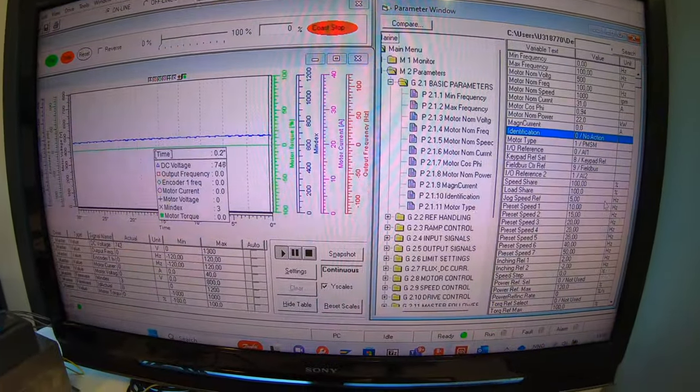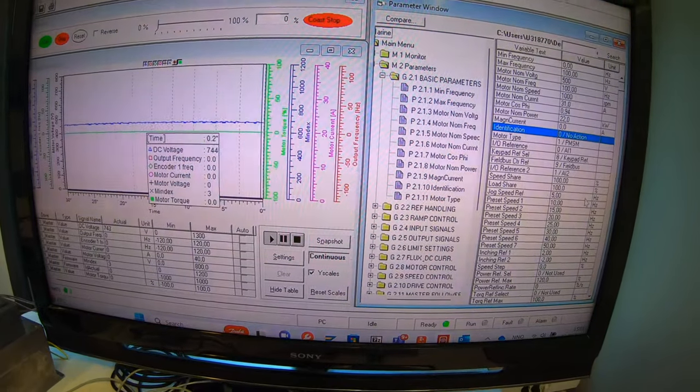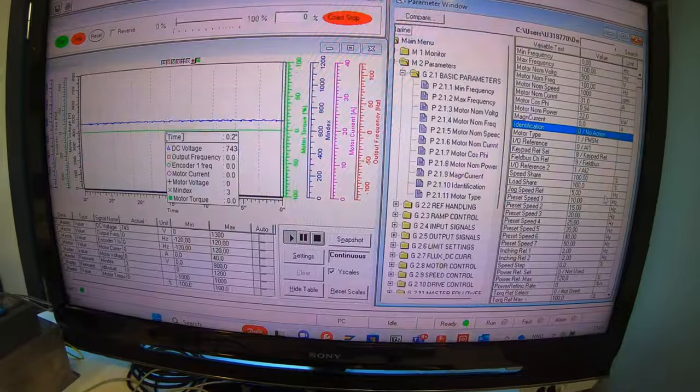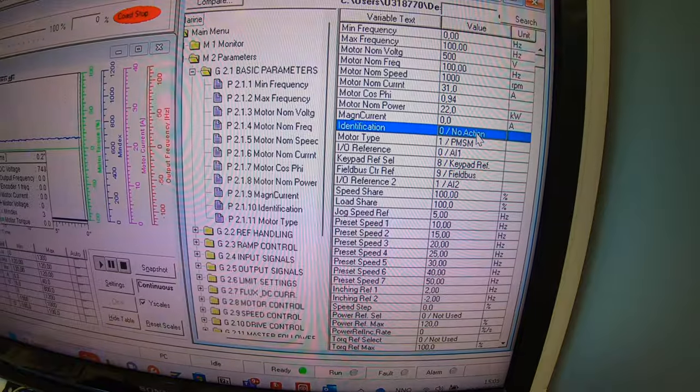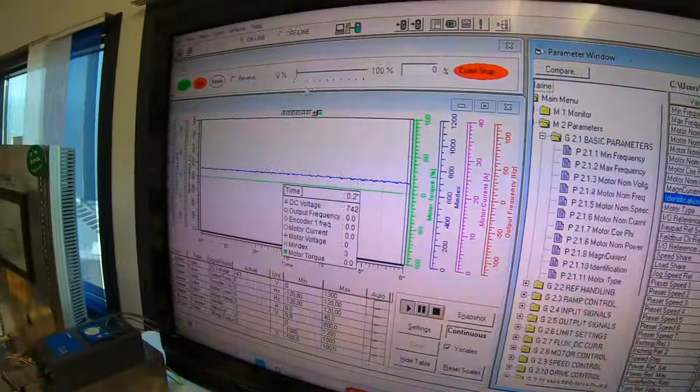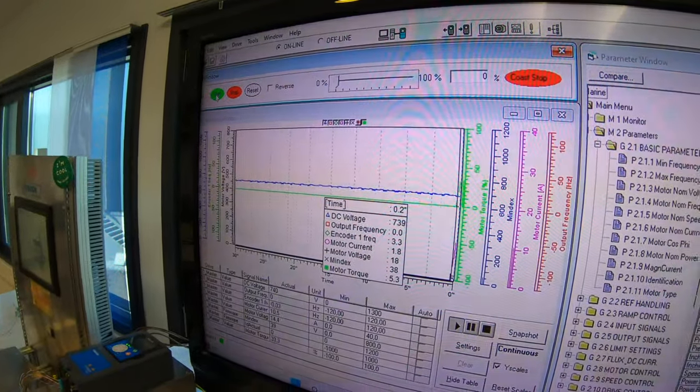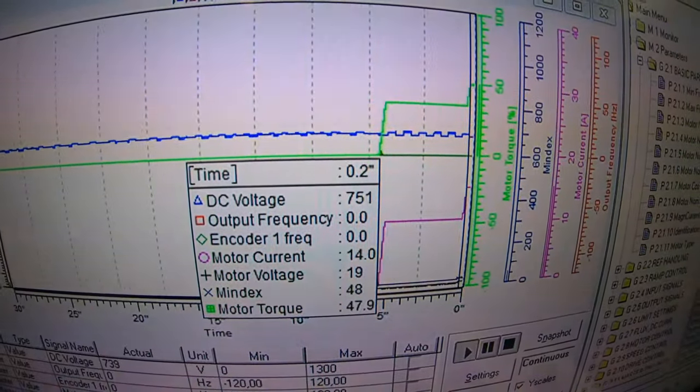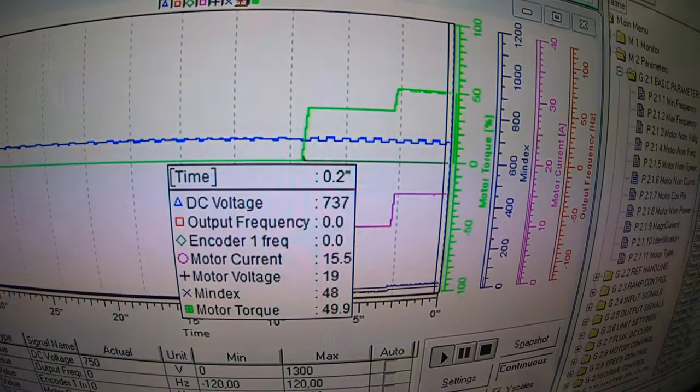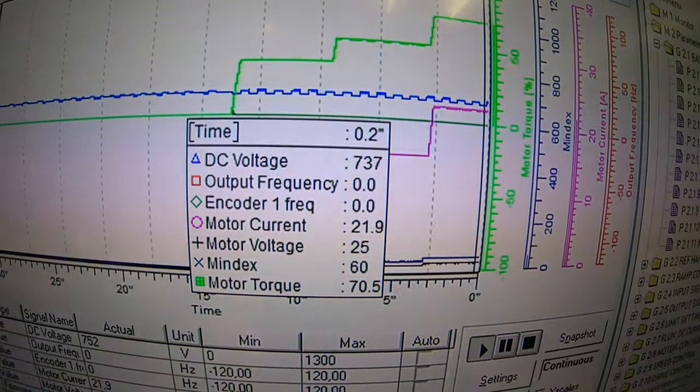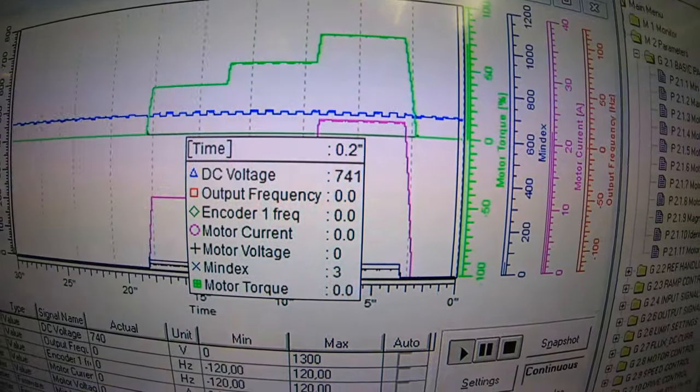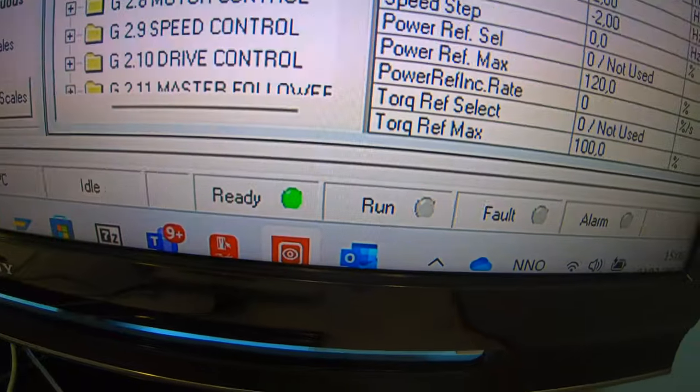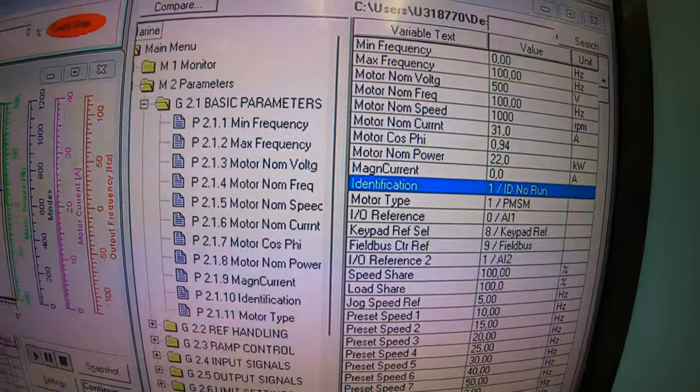We are now ready for doing the identification run without rotation. I have before this saved a parameter list so I have something to compare before and after the identification. I go to the basic parameters to the identification, and here I select ID no run. Then within 20 seconds I have to hit the start button. Here is a current going on, and what actually is going on is measuring of the impedance in the cables and the stator windings. So there is a quite big current going on, 21 ampere. Remember the nominal is 31. There are some strange sounds coming, and now it is finished. And here I can see from these symbols that there is no faults. So this went well.